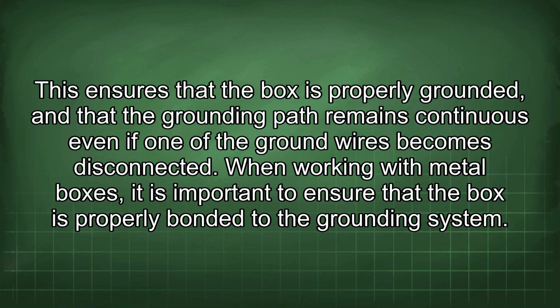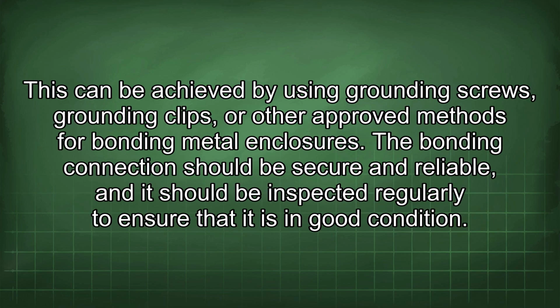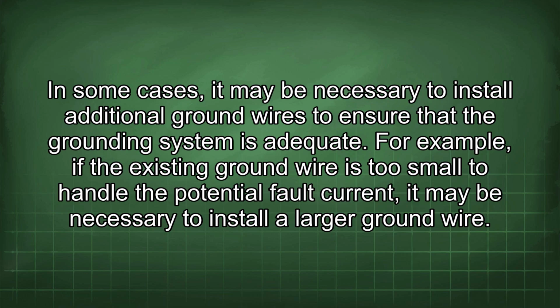When working with metal boxes, it is important to ensure that the box is properly bonded to the grounding system. This can be achieved by using grounding screws, grounding clips, or other approved methods for bonding metal enclosures. The bonding connection should be secure and reliable, and it should be inspected regularly to ensure that it is in good condition. In some cases, it may be necessary to install additional ground wires to ensure that the grounding system is adequate. For example, if the existing ground wire is too small to handle the potential fault current, it may be necessary to install a larger ground wire.